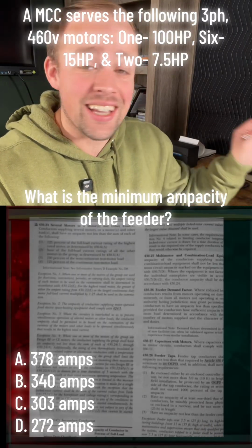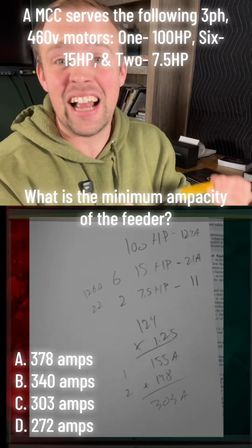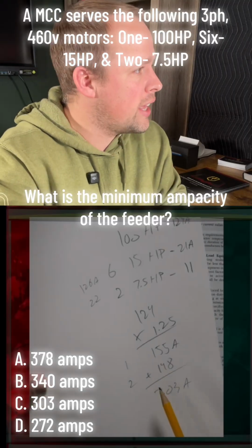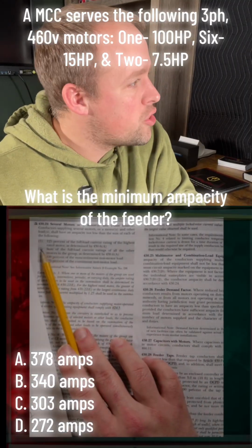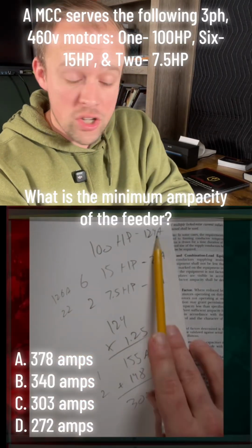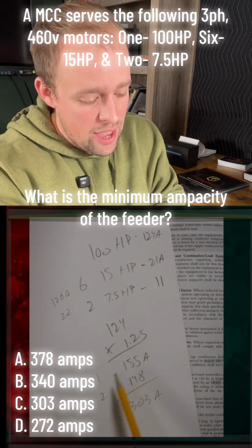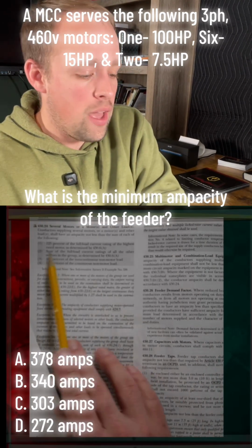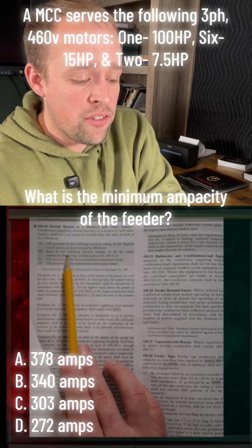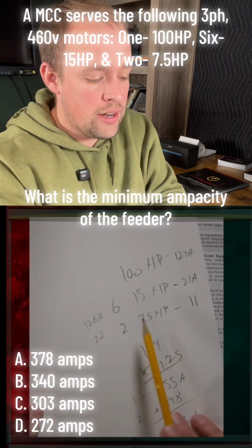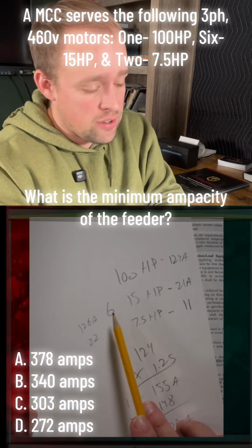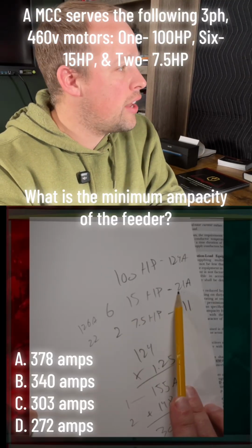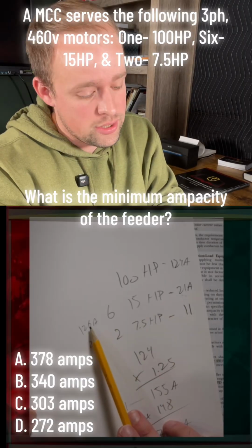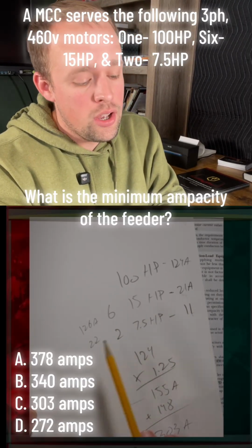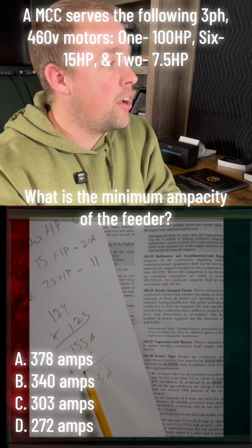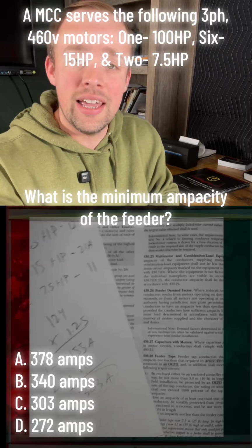Looking at my question, it looks like C is going to be my final answer. This is nice because it's exactly 303, so I am confident that this is my answer. But again, I want to explain what I did here. Number 1 is 125% of my largest motor. My largest motor was 124, took 125% of that, and so number 1 gives me 155 amps. Number 2 says the sum of the full load currents of all the other motors. So I took 6 21s. There were 6 15 horsepower motors, each one rated at 21, so 6 times 21 gave me 126 amps, and then there were 2 11 amp motors, so 22. Adding those together gave me 148. Adding those together, 303. That's going to be my final answer.